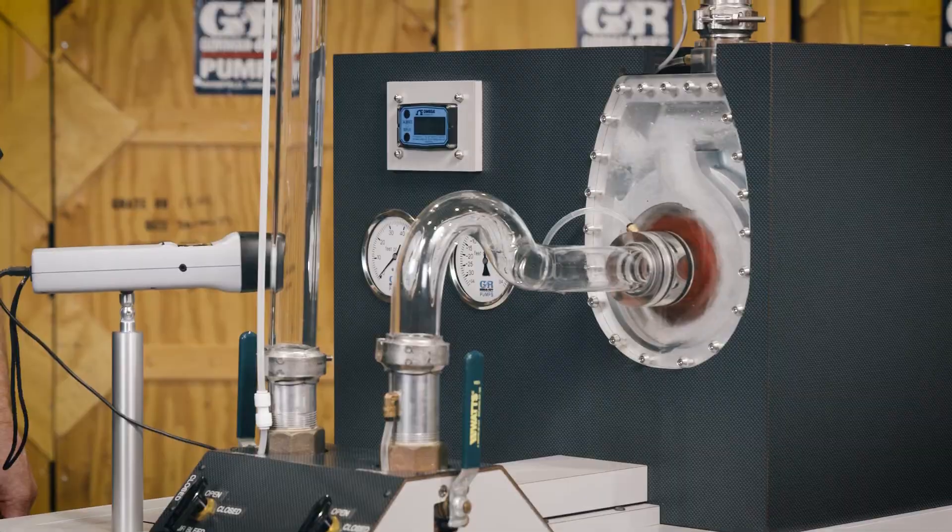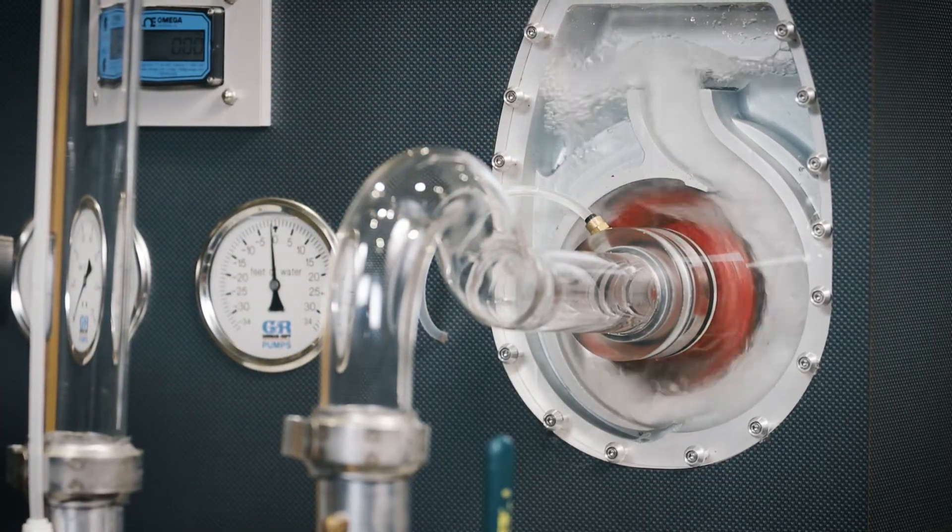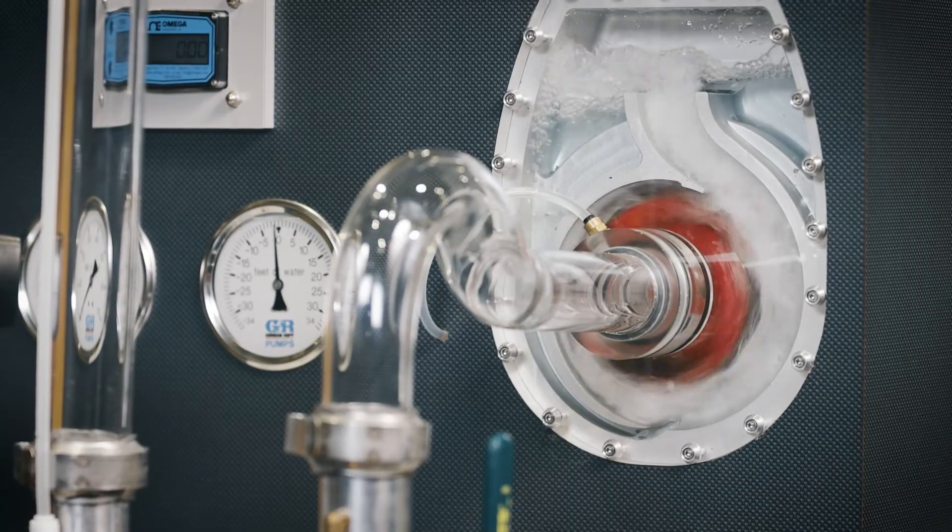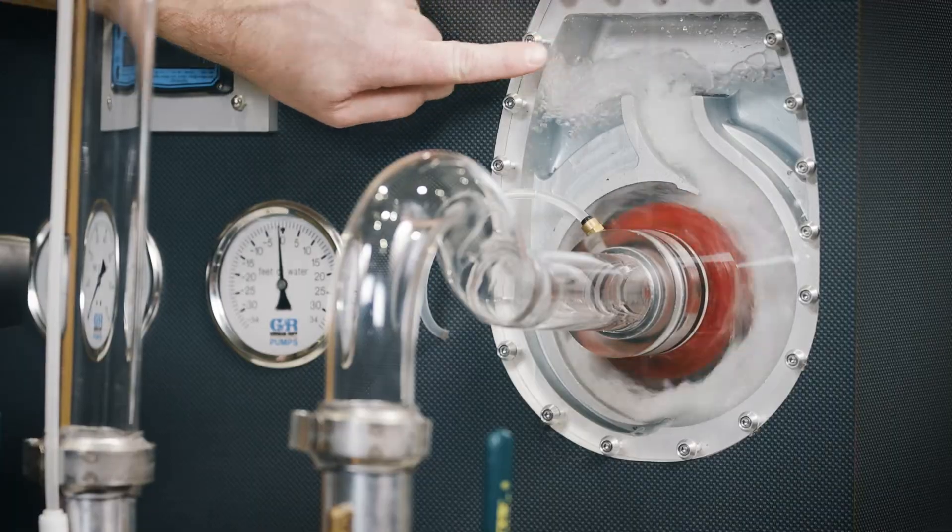As the air and water mixture enters the center or eye of the spinning impeller, centrifugal force throws the mixture to the outer diameter of the impeller, where it enters the water channel and is then expelled into the discharge chamber.